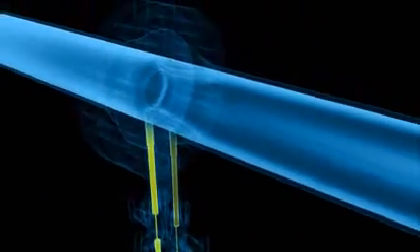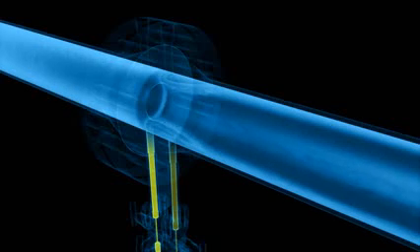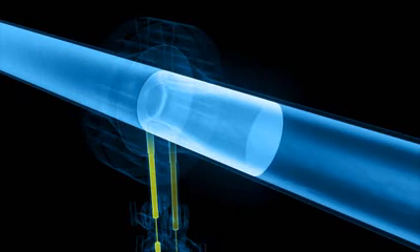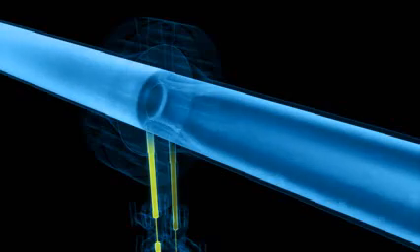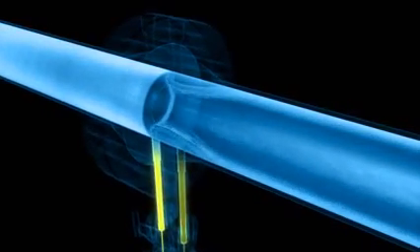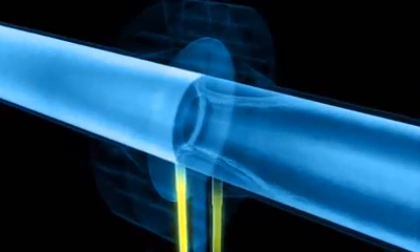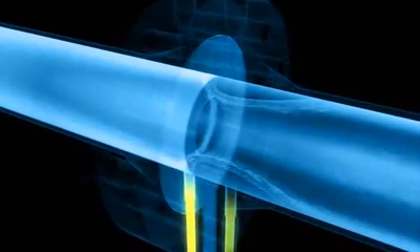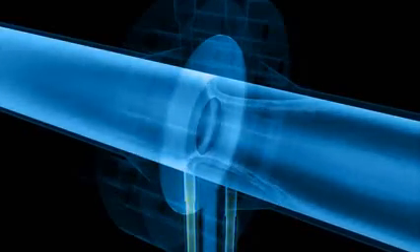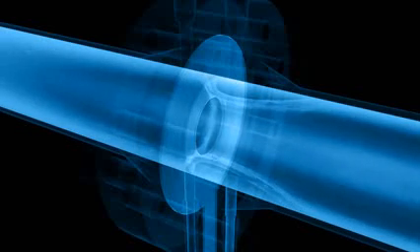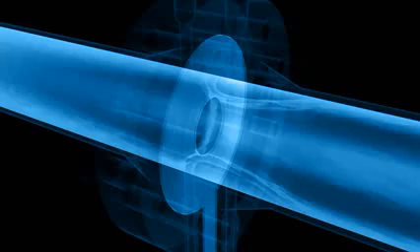This pressure difference is a direct measure for the flow velocity, and thus the mass and volume flow in the pipe. The higher the flow velocity, and the resulting drop in pressure around the orifice plate, the greater the differential pressure measured. In numerous industrial applications, the orifice plate covers many needs of flow measurement technology.